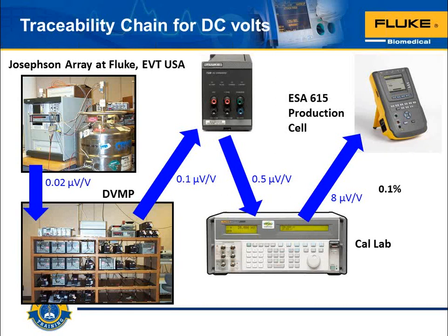And so for you, your traceability goes from the measurement that you're making with that electrical safety analyzer on a medical device all the way back through this unbroken chain to that Josephson's array, the original primary standard. And I hope that that helps you understand traceability and exactly the stack up of uncertainties. That's the little blue numbers in terms of how many tenths of a microvolt per volt that we have in terms of uncertainty. Our uncertainty is how sure are we that a DC volt is a DC volt and accurate back to the Josephson's array.